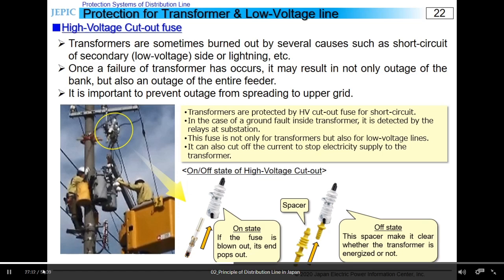High voltage cutout fuses are installed between high voltage line and transformer as shown in the picture for the protection of overcurrent. On the other hand, when a ground fault occurs due to an insulation failure of a transformer, it will be detected by ground fault relays in substation, resulting in an outage of the entire feeder. This fuse protects not only transformers but also low voltage line, and by insertion and removal of the fuse, it's possible to energize or unenergize the transformer.